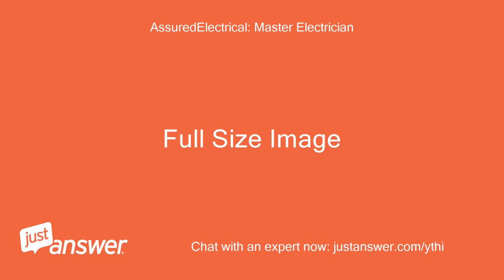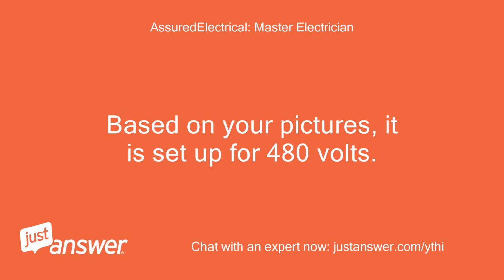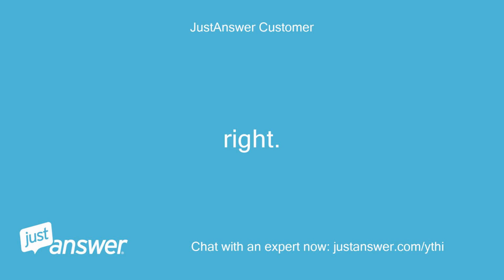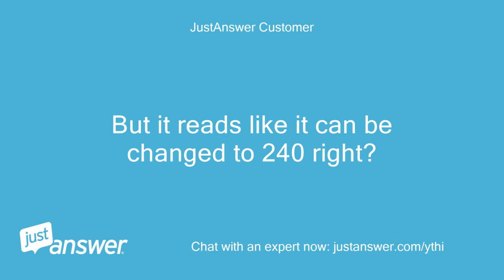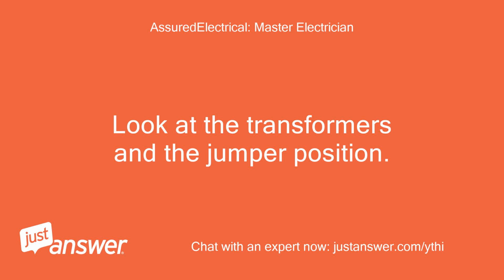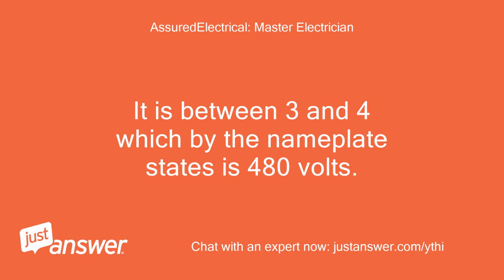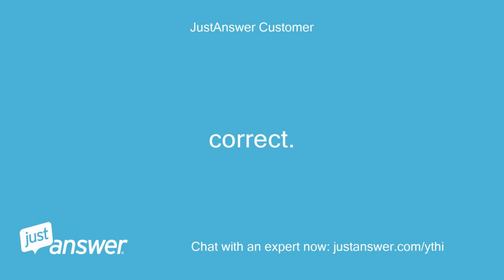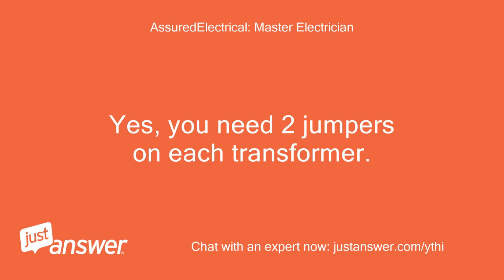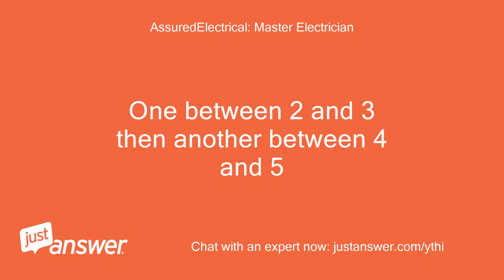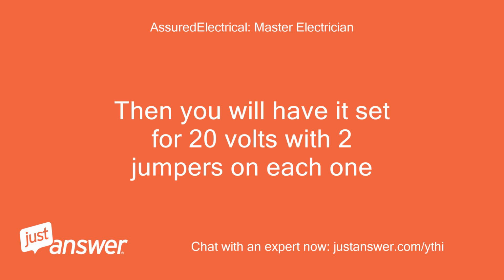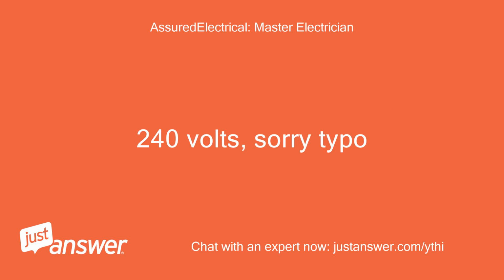Based on your pictures, it is set up for 480 volts. Right. But it reads like it can be changed to 240, right? Look at the transformers and the jumper position. It is between 3 and 4, which by the nameplate states is 480 volts. Correct. Yes, you need 2 jumpers on each transformer. One between 2 and 3, then another between 4 and 5. Then you will have it set for 240 volts with 2 jumpers on each one. Sorry, typo.